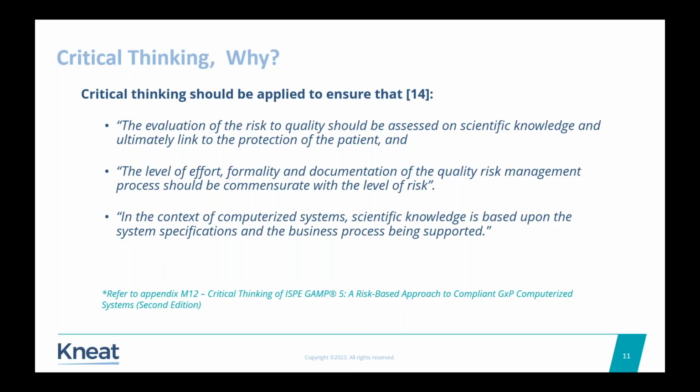So you're applying a documented risk-based approach to ensure the computer system fulfills the validation requirements of 21 CFR Part 820.70(i), which essentially means that if I use a particular piece of software in an automated process, I validate it, and I validate the appropriate level of risk using an established protocol, and these shall be documented. Okay, that's essentially what this means. Now, I've just mentioned the 21 CFR 820.70(i) regulation, right?